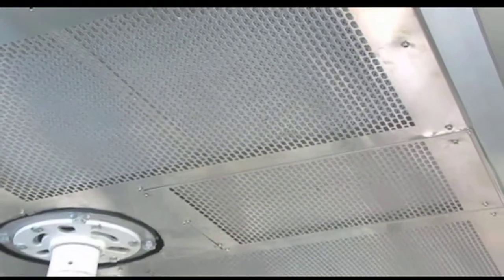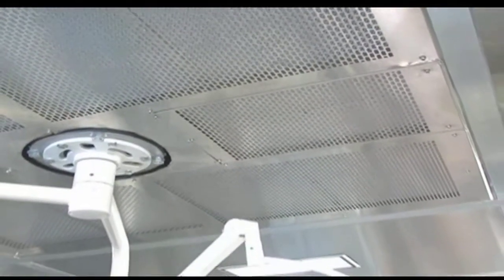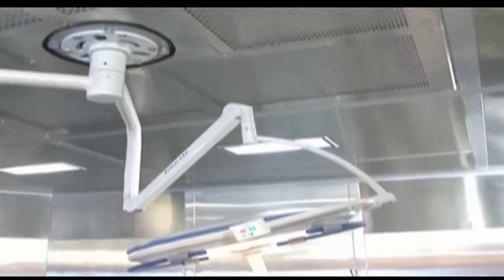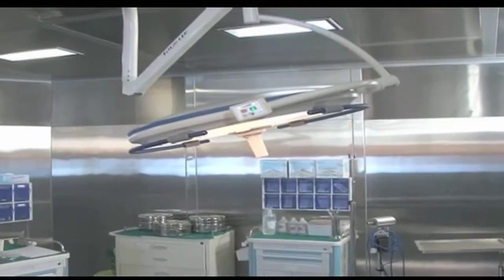The other thing that is characteristic about it is the way the theatre is ventilated. It always has positive pressure, so that whenever you open, for example, the doors, air would only flow out instead of in. The air on the inside is filtered to make sure there is no contamination.